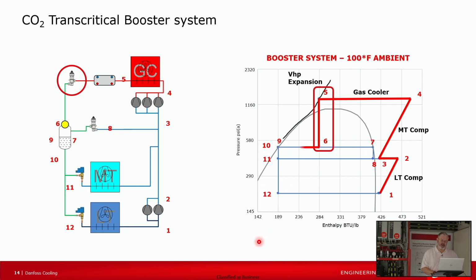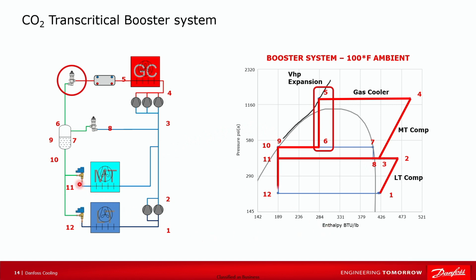So from the flash tank, we're going to exit the flash tank and enter the expansion valve for our medium temp evaporator. We go through the expansion valve, we boil off, and then we return a suction gas superheated back into medium temp suction here. And that's point 3 here on the left side. Then we're going to send liquid as well down to the low temp evaporator. Again, go across the expansion valve, boil off through the evaporator, and we come back to point 1, which is our low temp compressor suction inlet.